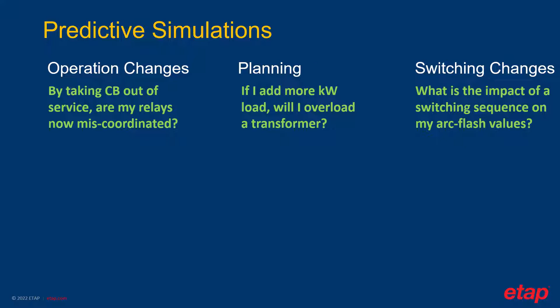Then we can evaluate the effects of switching changes. This could be switching from a servicing bus from A to B or taking a circuit breaker out of service. We would like to evaluate how will this impact my arc flash values. Note that all these changes we could evaluate offline. However, in this case, we can evaluate using actual operating values. This helps to review our simulation results with more confidence as we are considering the system as it's operating.